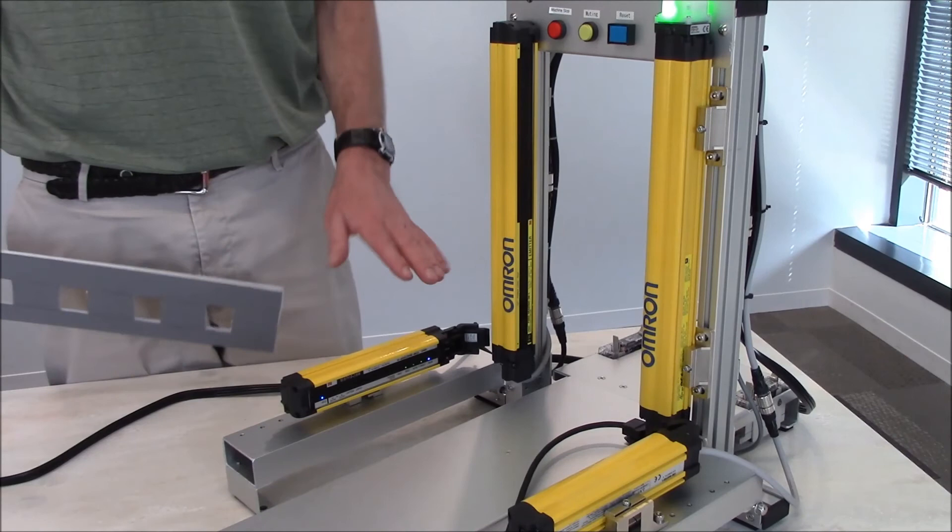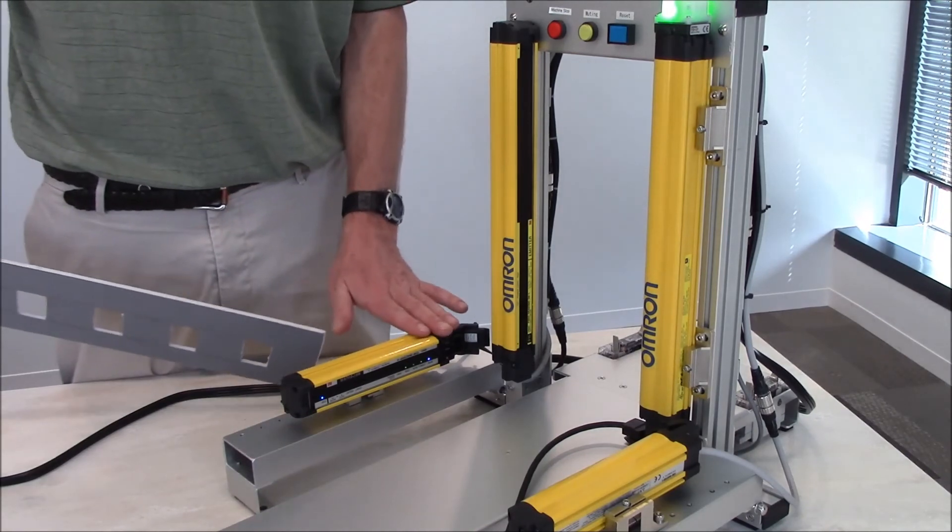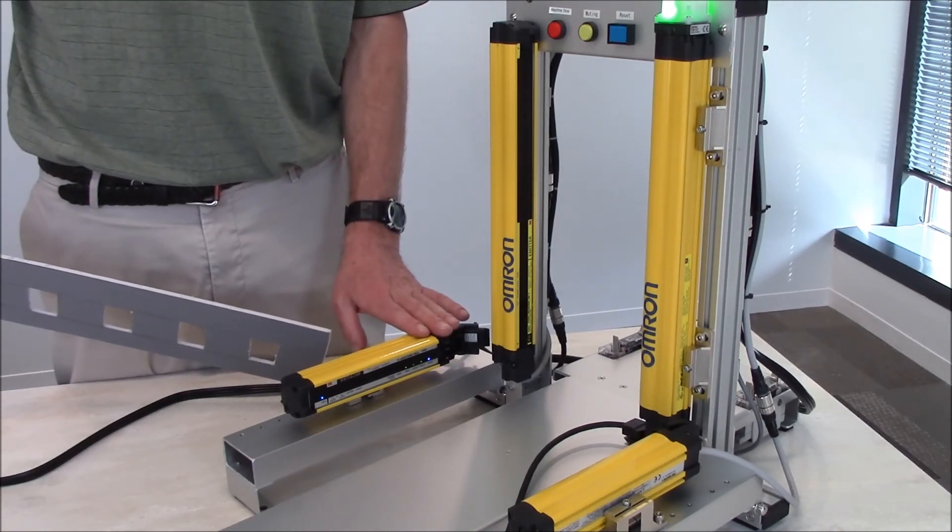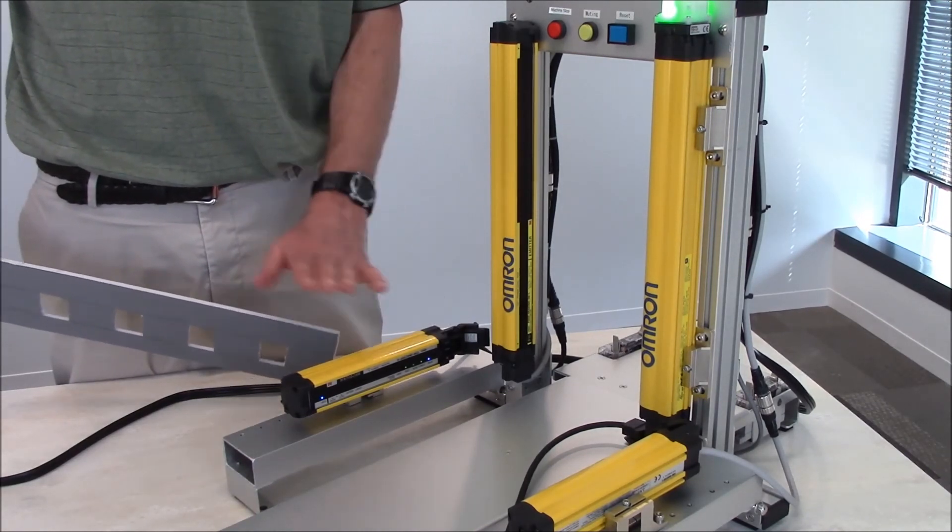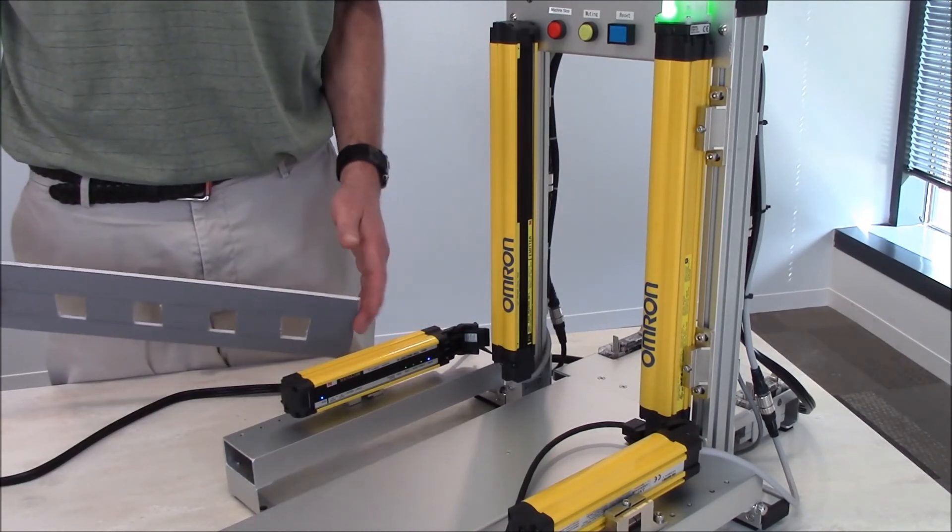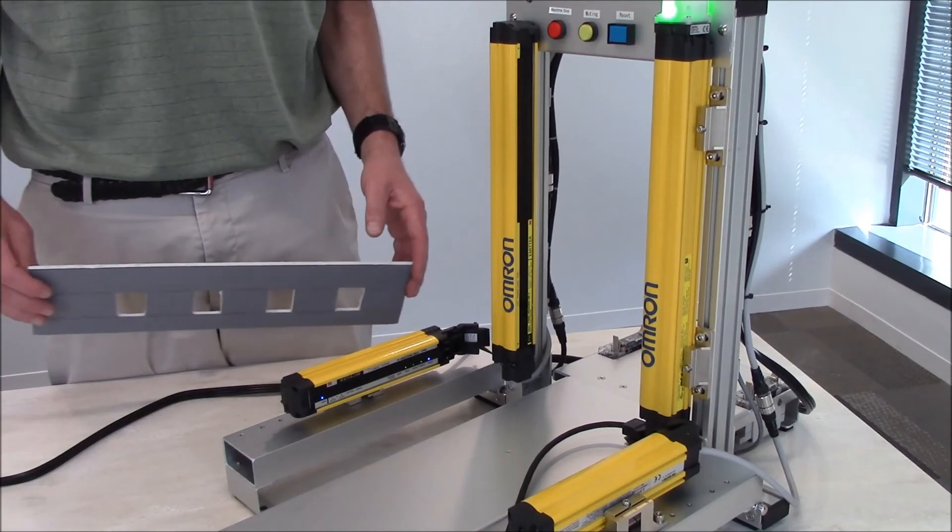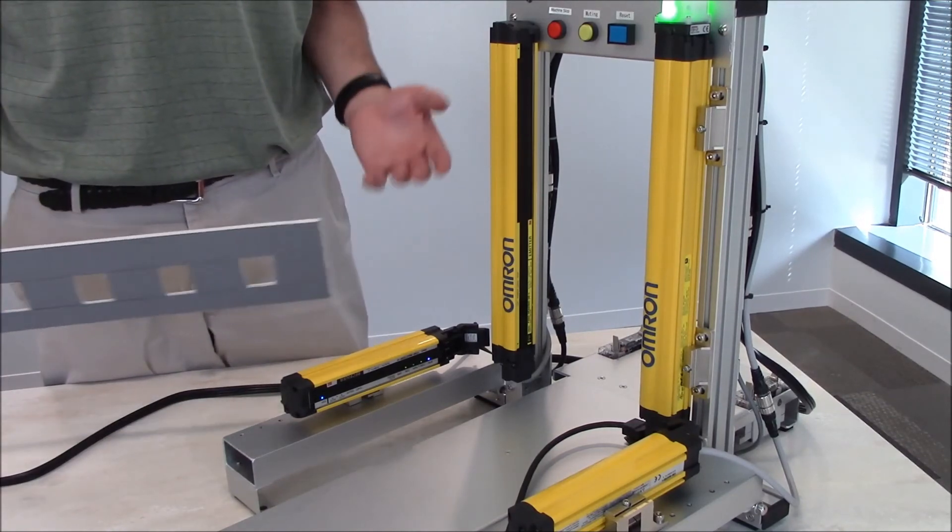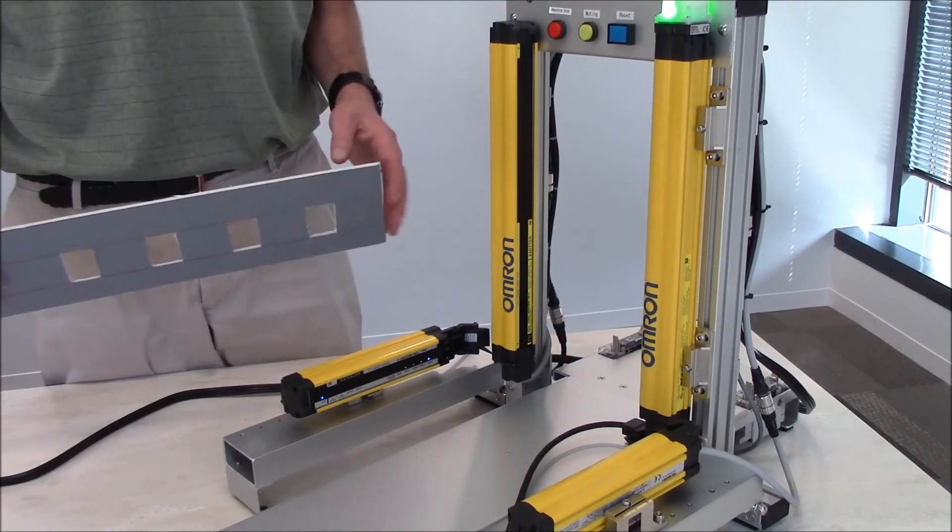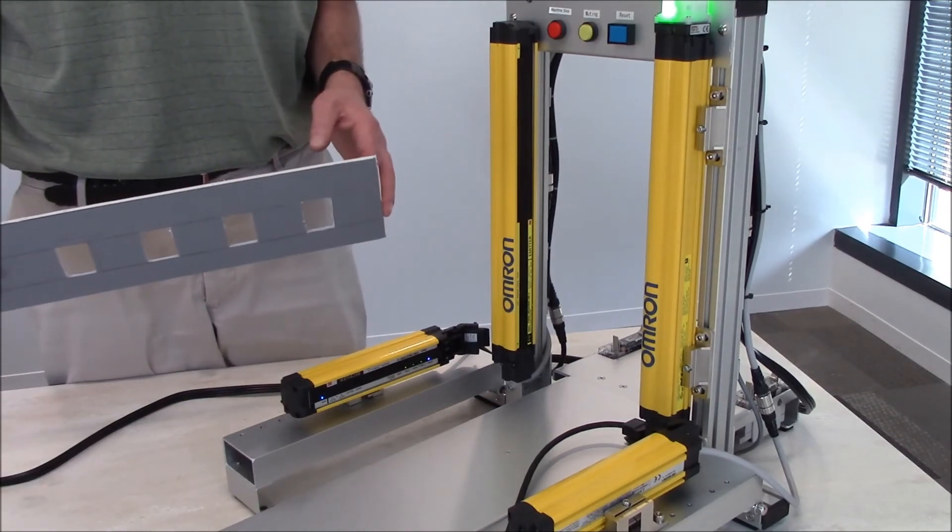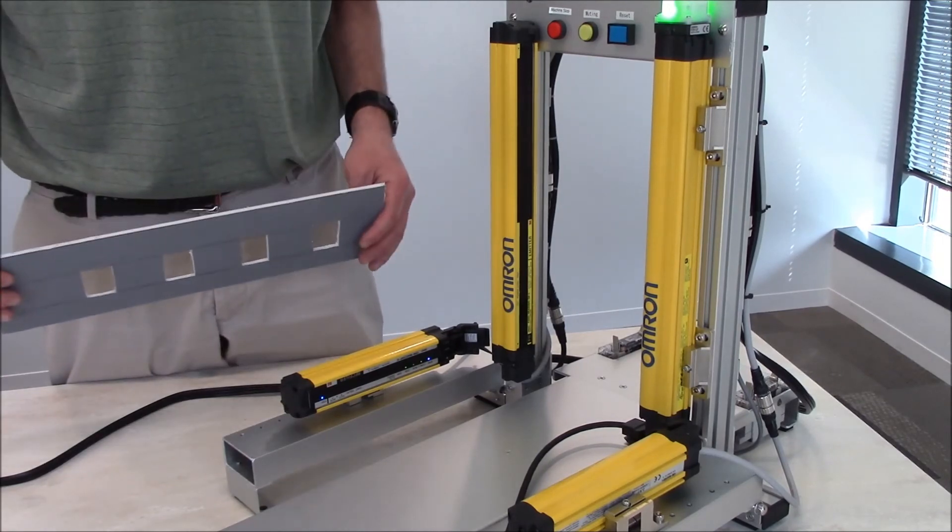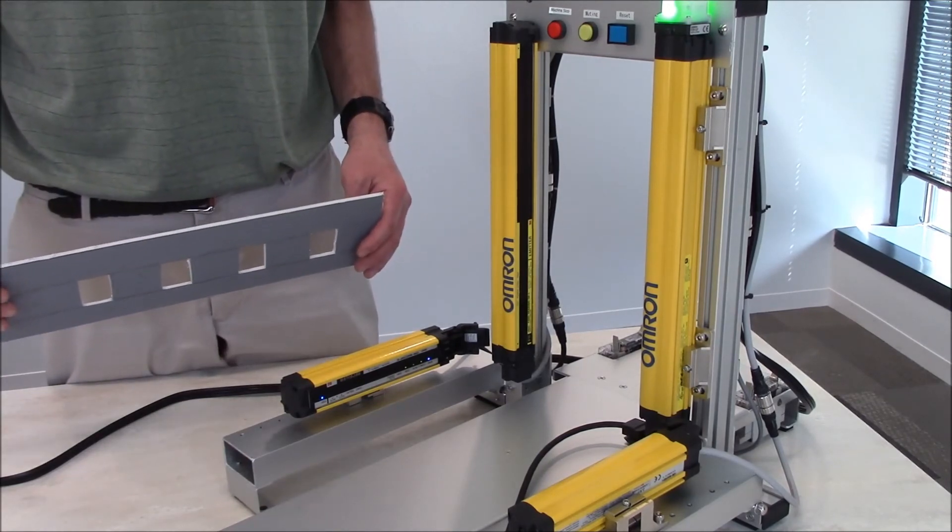Right now I have all of the dip switches in the off condition, so I'm not using the feature at this moment because I want to demonstrate how it can mess with the light curtain with these various different holes in the product.